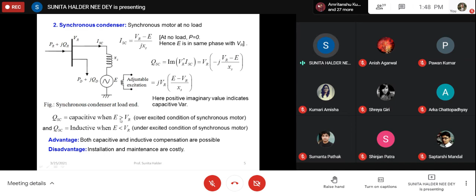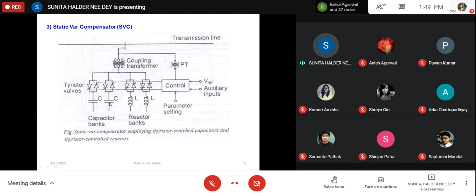And the static var compensator is a complete power electronics device. It is connected to a transmission line through a transformer. Through CT/PT, the current and voltages are sensed. Actually, it is nothing but a set of capacitors and a set of inductors in parallel, but their connections are controlled by thyristor valves. You know, in thyristor valves, until you give the gate signal, it will not turn on. So obviously, when this thyristor valve is in full conduction, then the capacitor current will be maximum. Similarly for inductor current. So by controlling this thyristor valve firing, you can control the effective inductive current and effective capacitive current. In that way, you can control whether this SVC will operate as an inductor or capacitor.